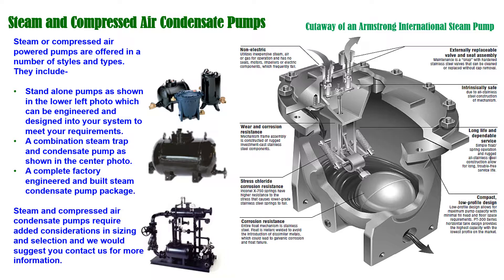Mechanical pumps can be operated by either steam or compressed air. They are of great value in applications where the condensate temperatures are in the 208 to 210 degrees Fahrenheit range, which would typically cause a motor driven pump to cavitate.